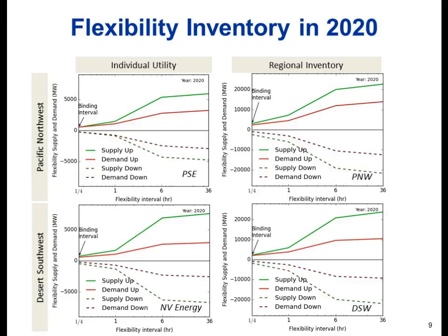Now, the question of whether those typical dispatch parameters that we've used in this analysis reflect the right starting point to begin with, I think that's the biggest challenge that we had with this. The typical dispatch parameters in this analysis were based on historical dispatch of generators. We had a few years of record of thermal power plant output during different load conditions, and we characterized that data set using these typical dispatch parameters. So we're building off of historical dispatch of power plants as that starting point.